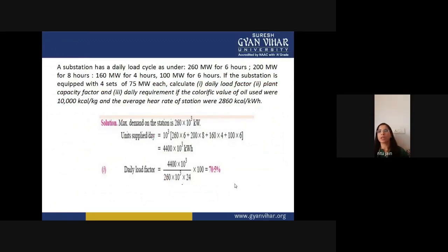Now, a substation has a daily load cycle as follows: 260 megawatt for 6 hours, 200 megawatt for 8 hours, and 160 megawatt for 4 hours. So different loads are given, and you have to calculate, if the substation is equipped with four units of 75 megawatt capacity each, the daily load factor, plant capacity factor, and daily fuel requirement. You are using oil as the fuel instead of coal. The calorific value of the oil used is 10,000 kilocalorie per kilogram, and the average heat rate of the station is 2,860 kilocalorie per kilowatt hour.